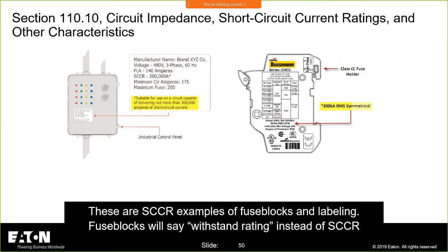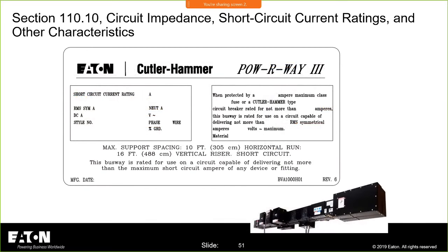Follow the instructions of the manufacturers, understand the short circuit current that's available at the equipment, and look for the labels that say short circuit current rating and what it's capable of. These all have a short circuit current rating. This is busway. It's a blank label, but you'll notice over on this side it will tell you when protected by a specific overcurrent protective device, whether it's a fuse or a circuit breaker, and it will tell you the exact size it needs to be. And it will tell you what type of short circuit current rating we have in regard to the rating of this equipment.